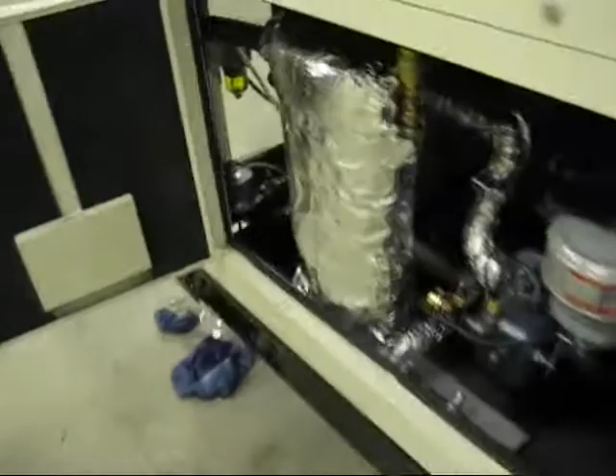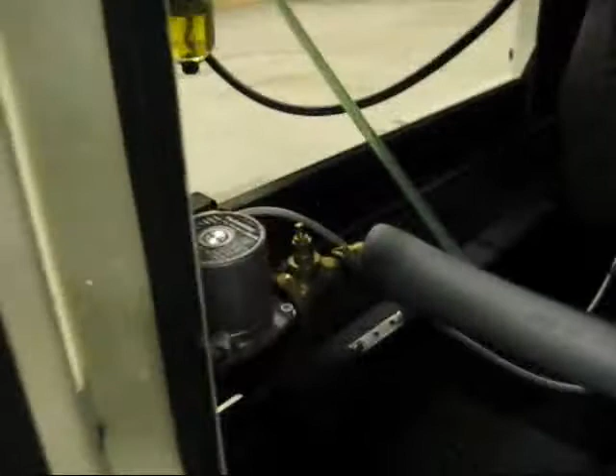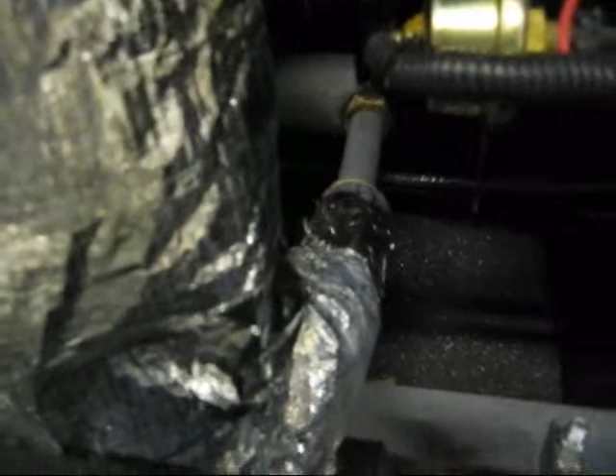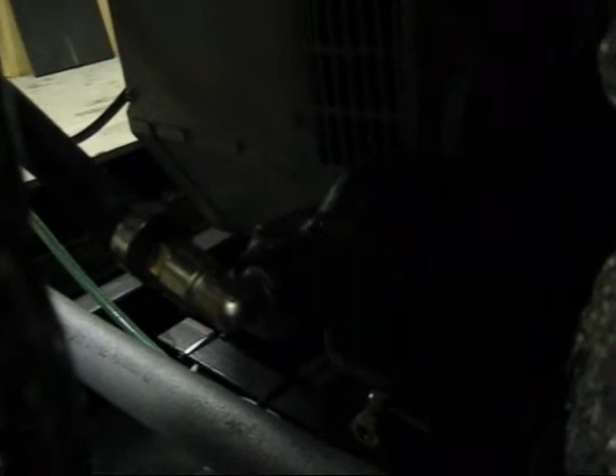Let's see if we can trace the water flow. So the return pipe at the bottom comes into the pump. The pipe flows into the exhaust gas heat exchanger near its entrance because it's cross flow. The hot water then comes out here, which makes its way to, I don't think we can see that, yes we can, to the engine mechanical water pump. Goes through the engine and out of this pipe here, which is insulated and works its way all the way up to the flow.